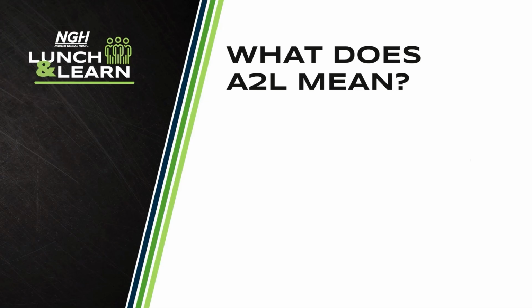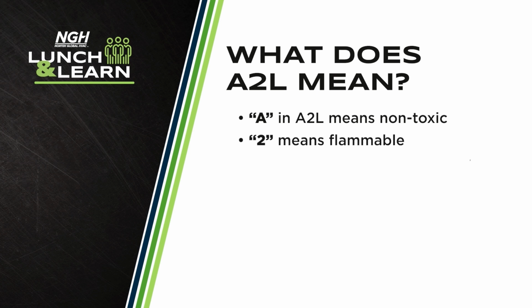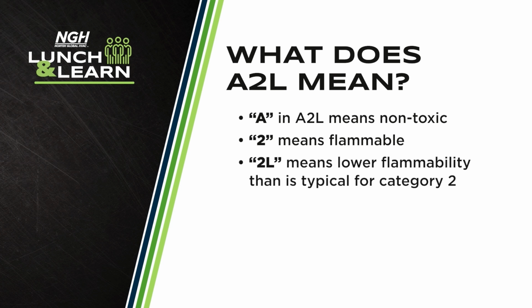What does A2L mean? ASHRAE 34 has classifications for both refrigerant toxicity and flammability. The first character indicates the gas's toxicity. The A in A2L means R454B is non-toxic, just like R410A. That's good news. The second digit indicates the flammability, and the 2 means R454B is flammable, unlike R410A, which is an A1. 2L means this refrigerant is lower in flammability than typical gases in the 2 category. Due to this mildly flammable designation, there are some things to consider during installation. The NGH engineering team has designed our new R454B equipment to help you make a successful installation while still maintaining our easy to install and easy to service feature set.